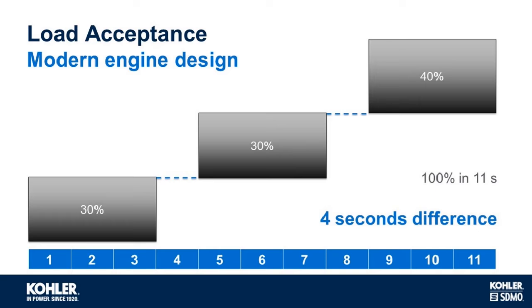A modern engine design, meeting emissions and all the other benefits that we've already talked about, has a 30% load step applied as per the ISO standard. It also recovers within 3 seconds. Then another 30% is applied, and finally a 40% load is applied, meaning that the generator is fully loaded to 100% in only 3 load steps and has recovered to steady state voltage and frequency within 11 seconds. So a difference of only 4 seconds overall.